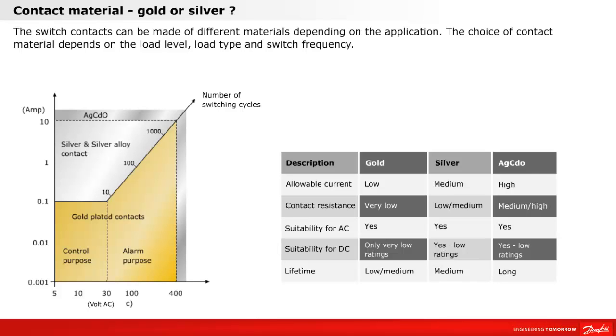The switch contacts can be made of different materials depending on the application. The choice of contact material depends on the load level, load type, and switch frequency. The diagram shows the recommended contact material in relation to voltage and current load. The arrow pointing up and to the right indicates the number of switching cycles. In control applications, there are typically high switching frequencies. For this application, gold contacts are recommended if the electrical load is low. For high electrical loads, silver or silver alloy, AGCDO, is recommended.